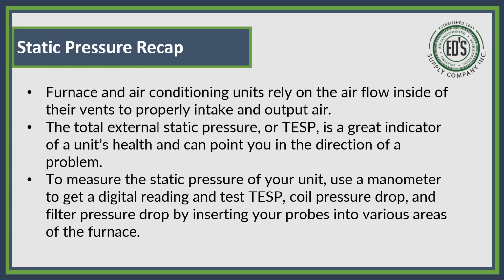Now, furnace and air conditioning units rely on airflow inside of their vents to properly intake and outtake air. The total external static pressure, or TESP, is the great indicator of a unit's health. Just like blood pressure is on a human body, static pressure is the blood pressure of a unit. Okay, and you can pinpoint where the problem is. If it's in my supply, is it a dirty coil? Is it no turning vanes? Is it small flex? Flex isn't pulled tight. Where's my resistance coming from?